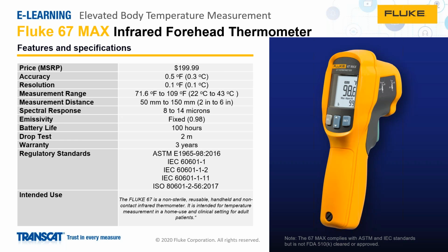in here are defined, tested to, and comply with the ASTM and IEC standards outlined in the FDA's enforcement policy. This includes 0.5 degree F accuracy, 0.1 degree F resolution, and a measurement temperature range, so what range of temperatures you might measure across the forehead, from 72 to 109, keeping the product at a 2-inch to 6-inch distance to remain within those stated specifications. We've talked about the emissivity. The battery life is 100 hours for this particular product, with a 2-meter drop test and a 3-year warranty, complying again with the standards that are stated here.